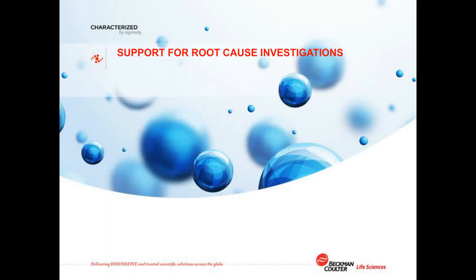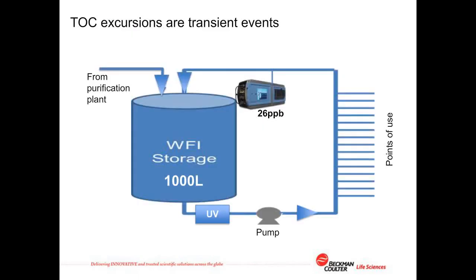Naturally, any TOC or conductivity excursion would lead to a root cause investigation. The problem is that TOC excursions can often be short, transient events, detected by the TOC analyzer, but disappearing by the time the team comes to take the water samples for root cause investigation. As stated earlier, 1 part per billion of carbon is equivalent to 1 microgram per liter of carbon in a liter of water. So let's take a look at a typical situation.